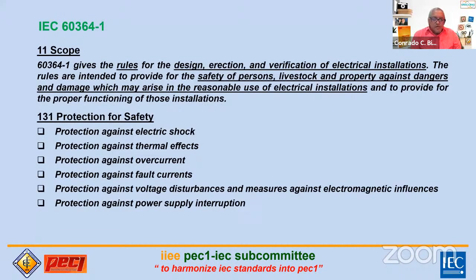So let go ay okay pa rin yon. But when it comes to 30 milliamperes, delikado na yon, di ba? But the IEC standards also, when it comes to against electric shock, ginagamit 30 milliamperes. So between 40, ito yung heart natin, yung VF, ventricular fibrillation, ay meron siyang 40, then merong 30 milliamperes. So nagkaroon ng allowance sa IEC standard, but merong consideration ang element of time. It should be very fast, to open the circuit, less than 200 milliseconds.